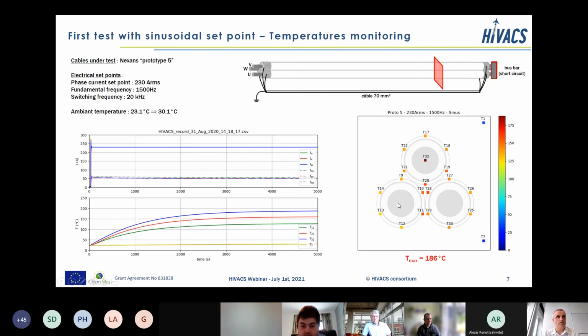So now, if we look at the thermal evolution, in this slide you see the thermal test. First of all, we need a long time duration to wait for a steady state temperature, so more than 1 hour. If you look at the top graph, you can see the regulation. With our inverter, we keep the same value of the current during all the tests. It's a sense current, a recording current, and it's important to check that because of course there is an evolution of the resistivity with the temperature. And we need a permanent regulation to keep the same current in the conductor.